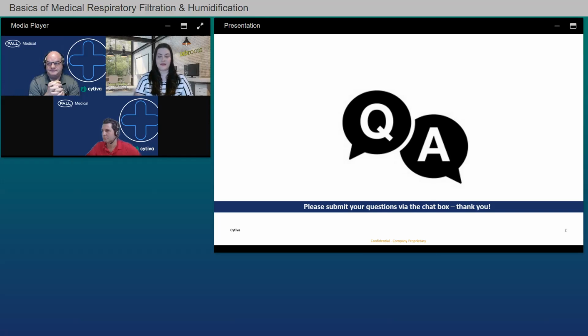Wonderful, thank you. All right, our next question says, you talked about the BB100. Do you have other filters, and do they have the same humidification? As mentioned early on, we have three main categories. That's the BB25, the small one, with about a 35 milliliter volume. Then we have the BB100, about 85 milliliter, and the UltraPro 50, about 50 milliliter, somewhere in between. And as I said, they're for different applications.